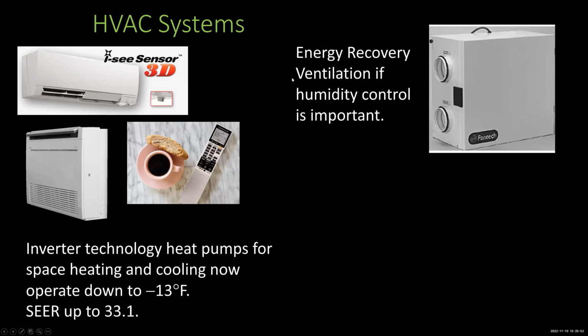Here's some more stuff, an energy recovery ventilation system. This is a very simple countercurrent heat exchanger that brings in outside air and vents out inside air. If the outside air is cold and the inside air is warm, the inside air leaving warms the cold air coming in, so it's warmer, and vice versa.